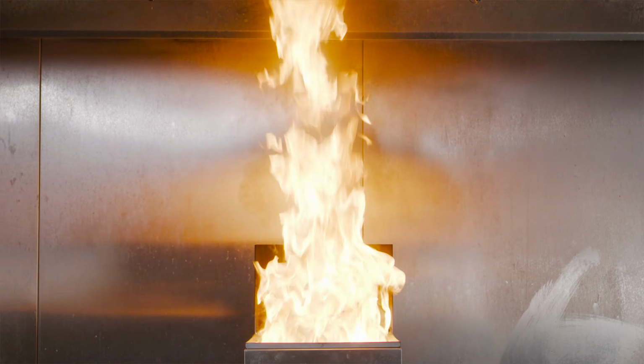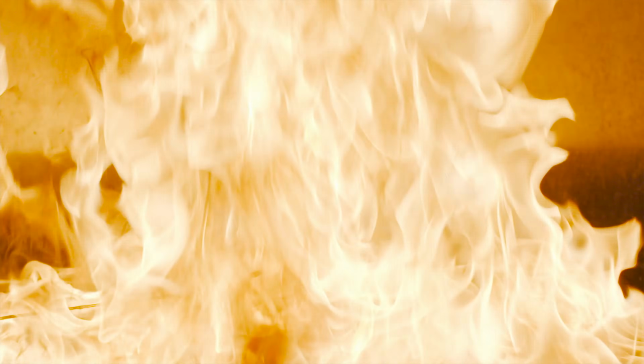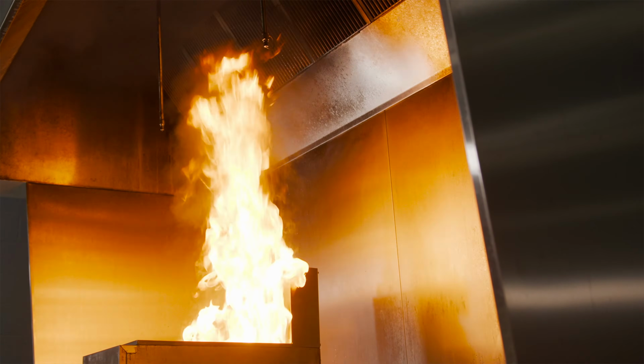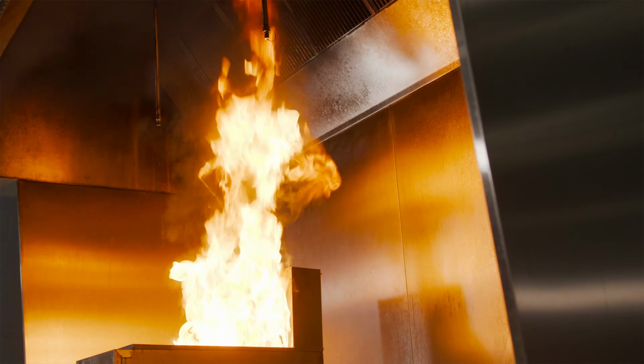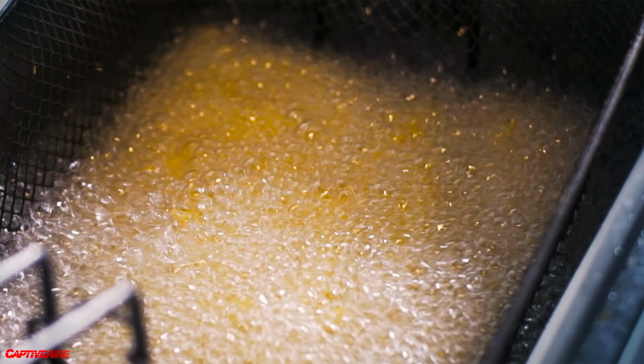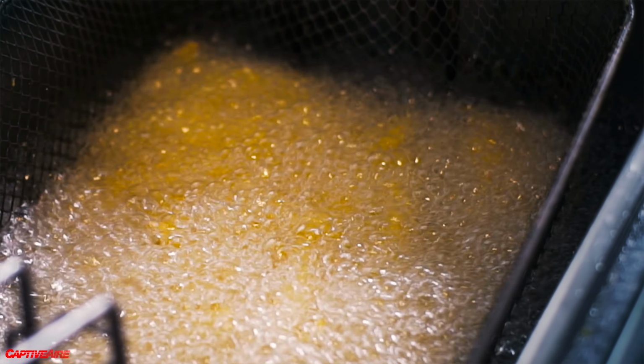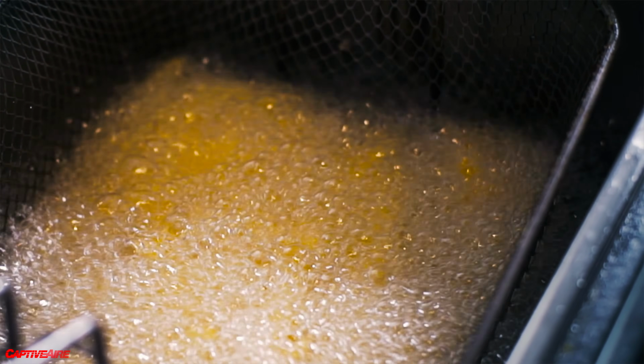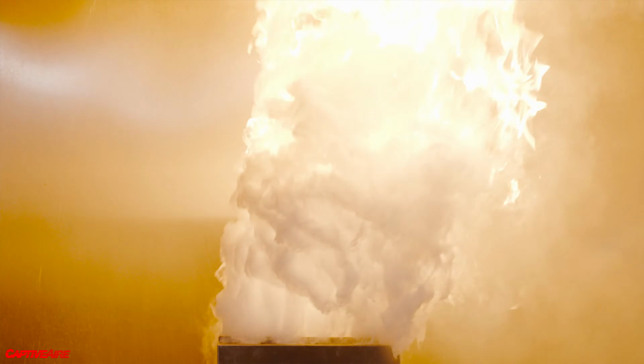It's a runaway train kind of fire. Trying to put this out with a fixed amount of dry chemical agent is not likely to happen. The oil is bubbling, so there's just no way a thin blanket of chemical will stay put enough to suffocate the fire and put it out without cooling the oil in the first place.